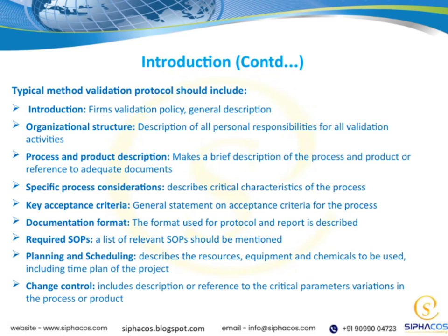Following that, we define the key acceptance criteria. This is where we establish the general standards or benchmarks that the process must meet to be considered successful. The documentation format is also covered, describing the structure and format used for the protocol and the final report. Consistent documentation is essential for regulatory compliance and future reference. We then list the required SOPs, standard operating procedures, that are relevant to the validation process. These SOPs guide the activities and ensure consistency across validation efforts.